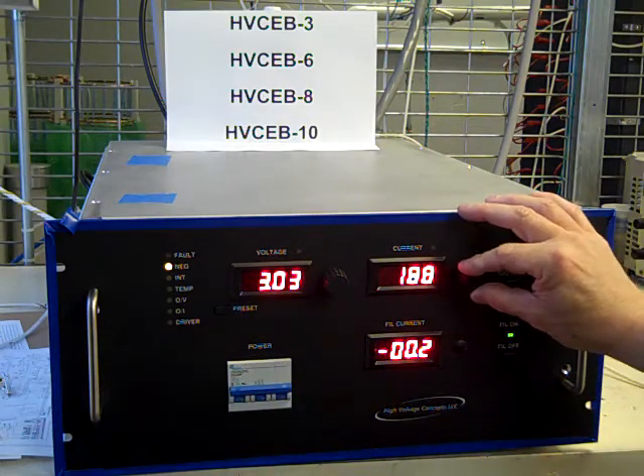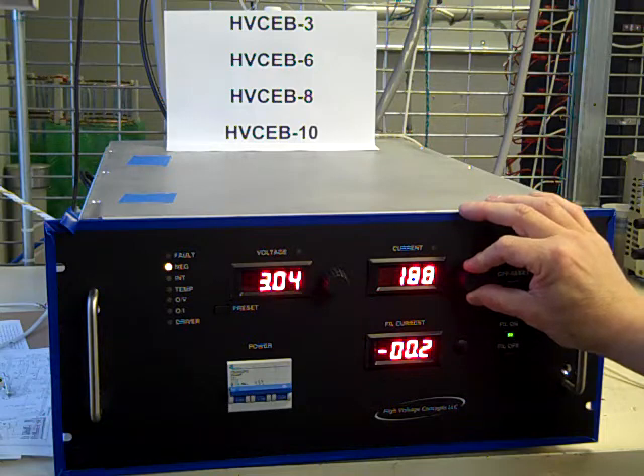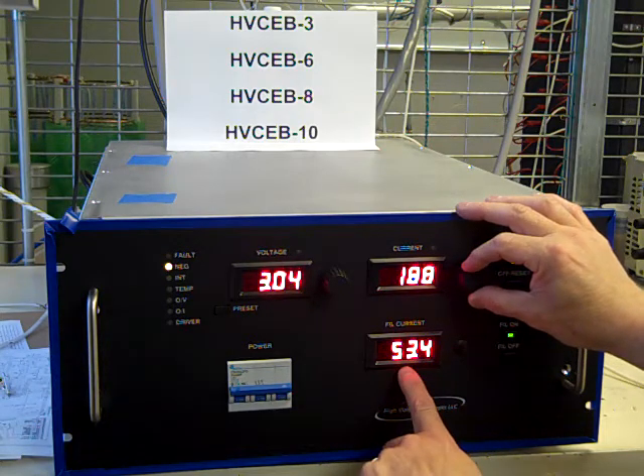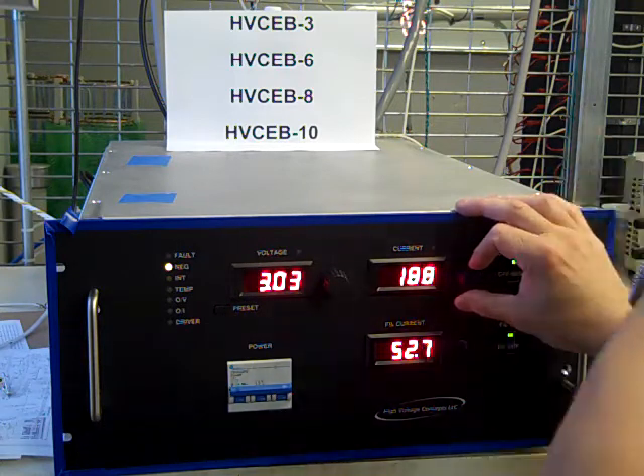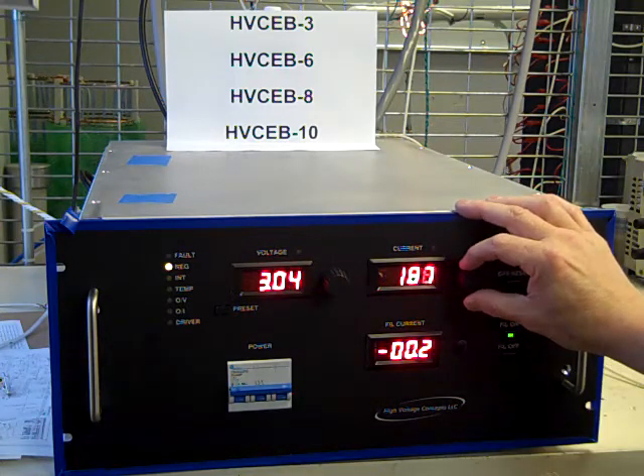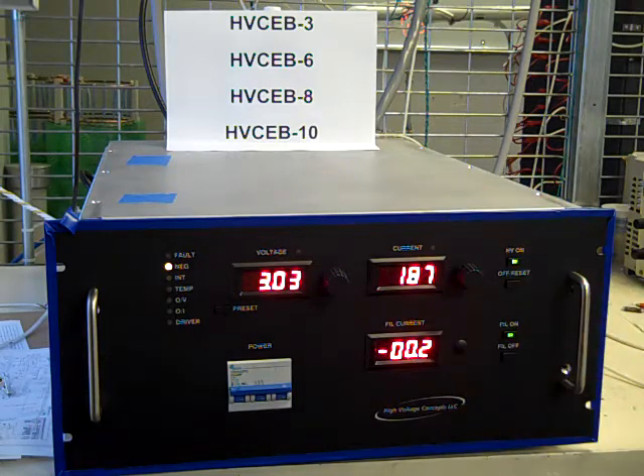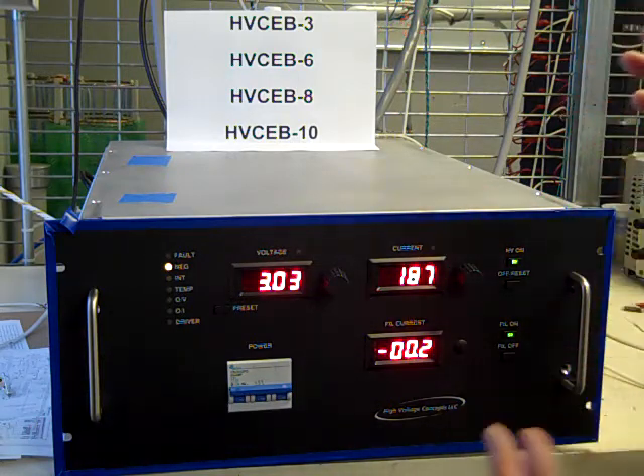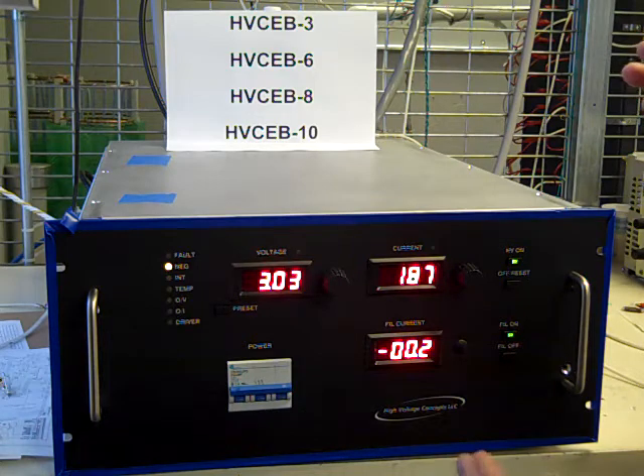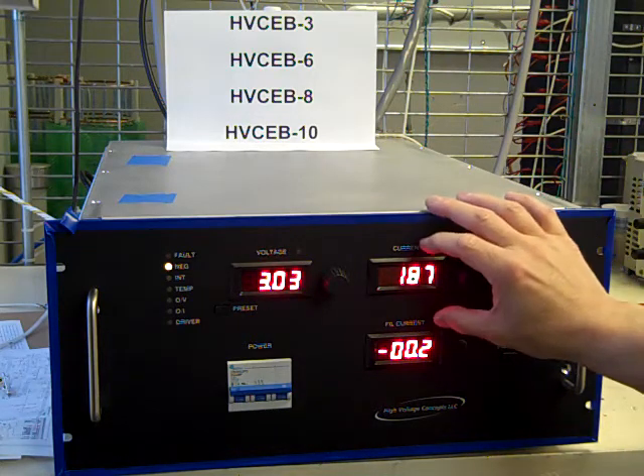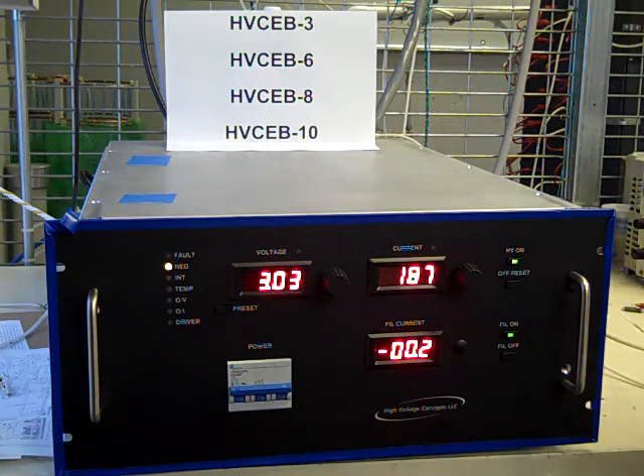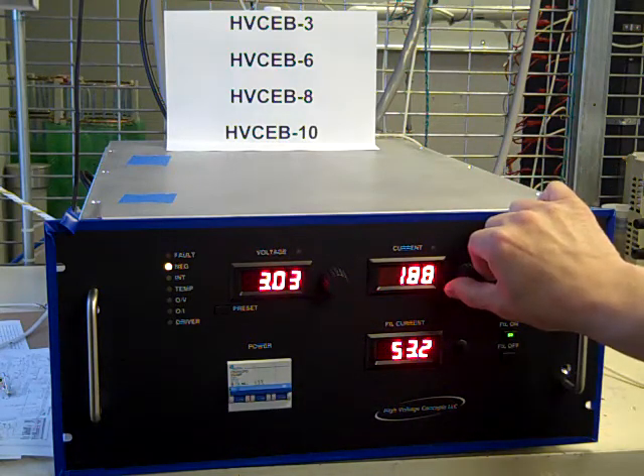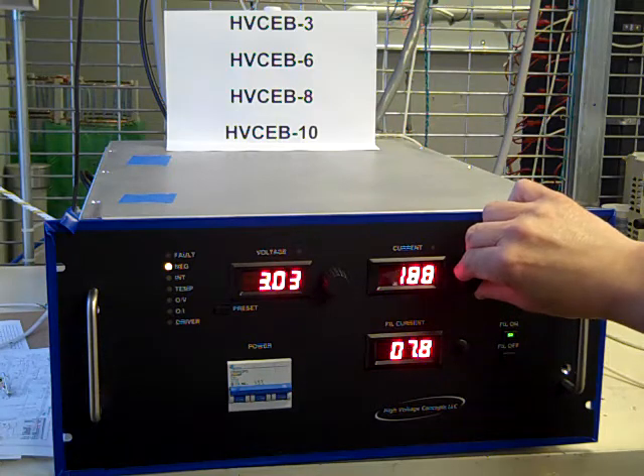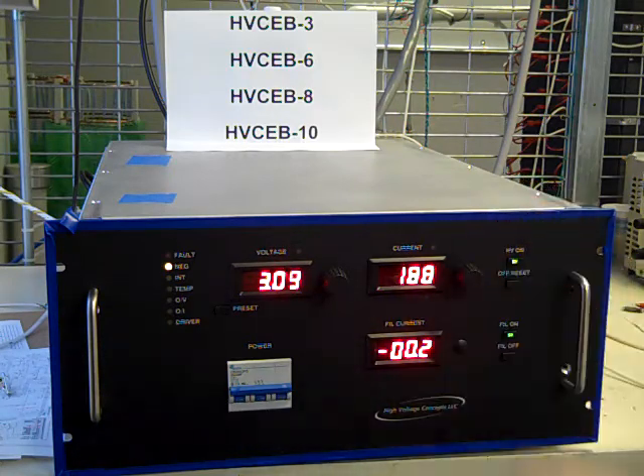If I raise up the set point, and this is on a resistive load, what happens is you see the filament turn on hard to try to make electrons to get up. It can't do that because we're not on a gun. If I go below that set point level, the filament turns off. This is what you're seeing, the regulation of the filament to make current on the output. The current is fixed here because we have a fixed resistor and we're not on a gun. So that's why if I raise this up, you see that filament turn on. If I go below the set point, you see the filament turn off.